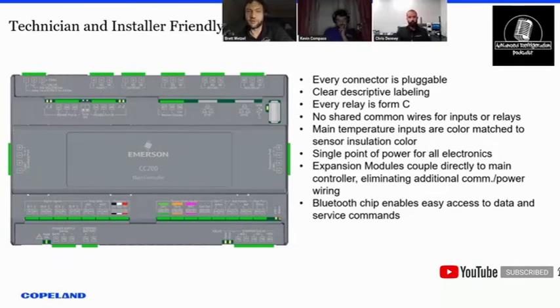That's interesting because with the XM 678, 679, if you would have a shorted valve where it just pulsed the voltage, it would go straight to ground and then take the PID board out. But now that I'm thinking about it, after all the CC100s I've ever worked on, I've never actually once seen that. Yeah, that was an issue we knew we had to keep eliminated on the hardware, and so those guys did a great job on the electrical design.